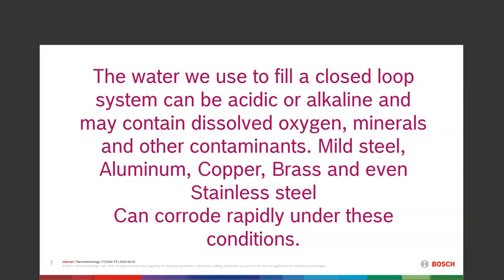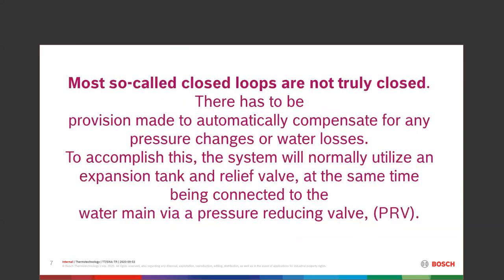Anytime we have dissolved oxygen, minerals, or other contaminants, mild steel, copper, brass, even stainless will corrode pretty rapidly. We've actually seen boilers that are a year or two old in very bad water conditions that already have pinholes in them. When we replace a boiler under warranty because it's got a pinhole and in another six months the replacement is doing the same thing, we have a problem. You're not going to see any warranty coverage if there's a water chemistry issue.